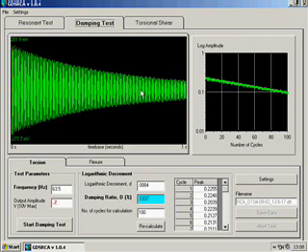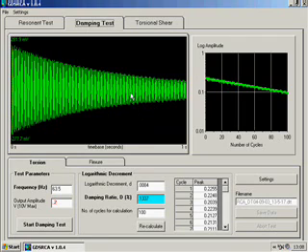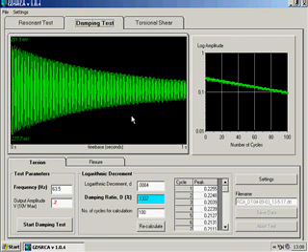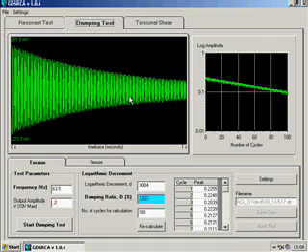The apparatus was designed to minimize equipment damping. During free vibration decay, after the power is normally shut off at resonance, a back EMF is usually generated in the coils by the movement of the magnets. This causes large equipment damping errors. In the GDS resonant column, the software can switch the hardware to provide an open circuit during free vibration decay, which prevents the back EMF generation.